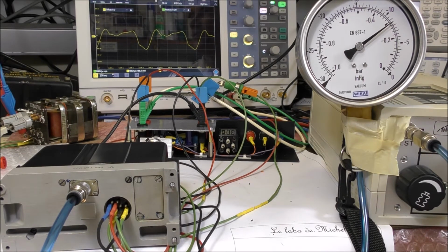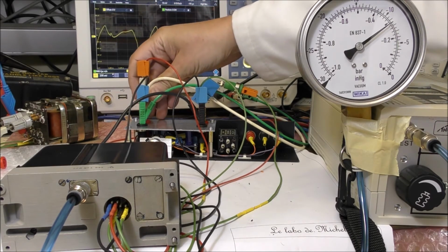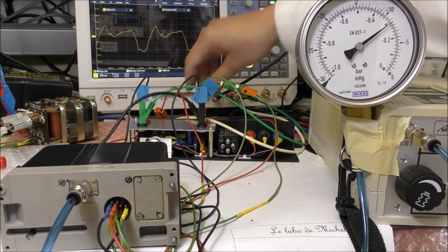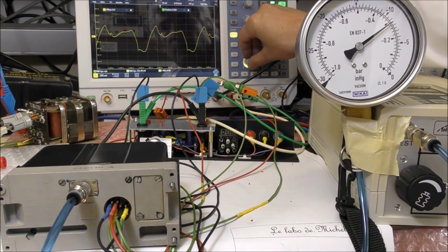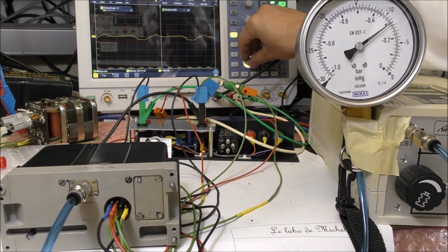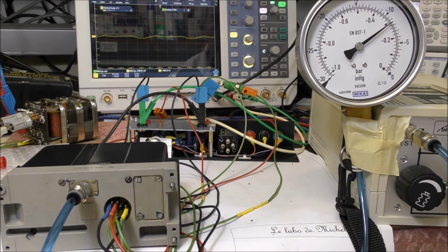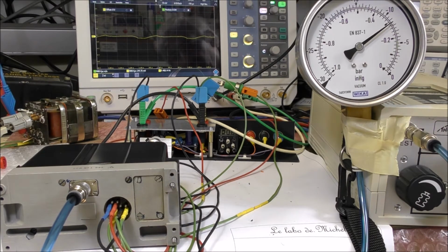So I will disconnect the input of the amplifier. It's just this wire here. So there is no change at this time. I will decrease the sensitivity. Okay, so the pressure now is 288 millibars. Nearly 300 millibars. Below, of course, the room pressure. So that is to say, a pressure of 700 millibars or something like that. So now we'll decrease the pressure.